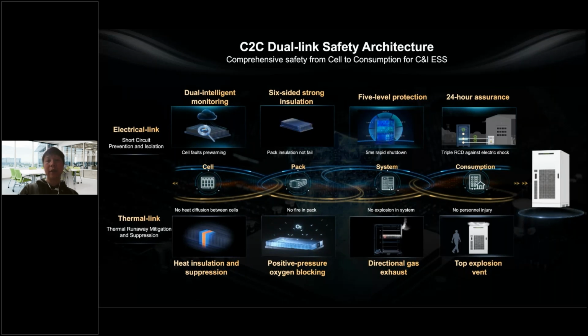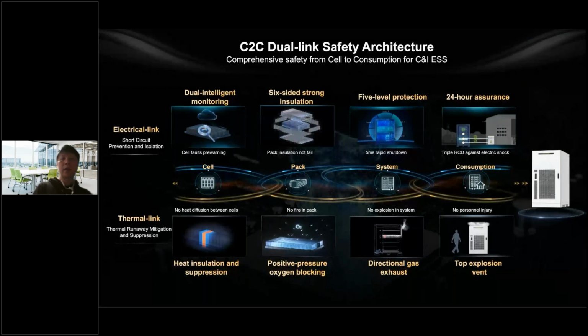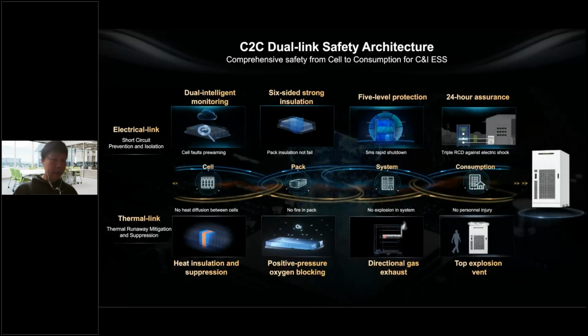So which means if there's a battery cell thermal runaway, we can release this pressure from the battery pack, and also we have this kind of directional gas exhaust, so the pressure will be released from the battery pack and eventually exhausted from the battery cabinet. This way, it will make sure the battery pack will not have an explosion, and there's no explosion inside the cabinet.